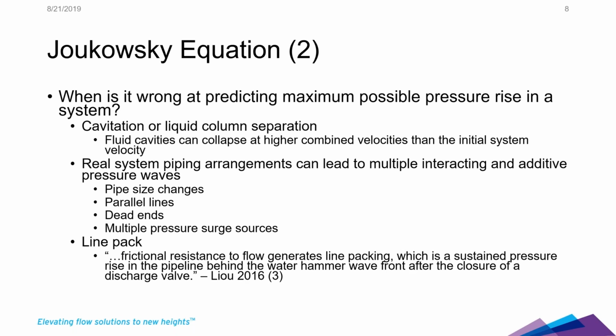Typically, those are worse with what I would call square wave behavior if you're looking at your pressure profile animation. If the wave front is steeper, your dead ends are going to be more significant. They're going to cause more issues.